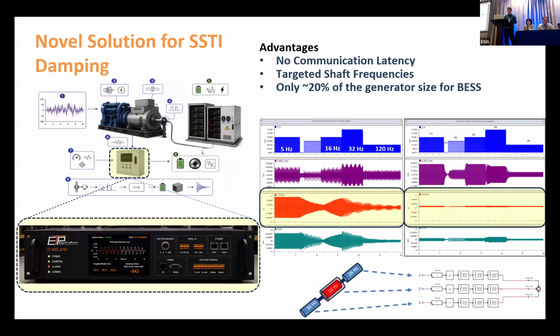So they also had the issue of subsynchronous torsional impact between the gensets in the facility and the AI loads. We have our patent-pending IT SSO 555, which is a generator-centric solution, because you don't need a 100 megawatt battery to damp oscillations or torsional impacts on a 100 megawatt genset. You can have a dedicated battery for the generator. With this solution, we were able to help our client. As you can see on this plot, with our solution we were able to effectively damp the subsynchronous torsional impact on the generator on different load profiles with different amplitudes and frequencies of oscillation.